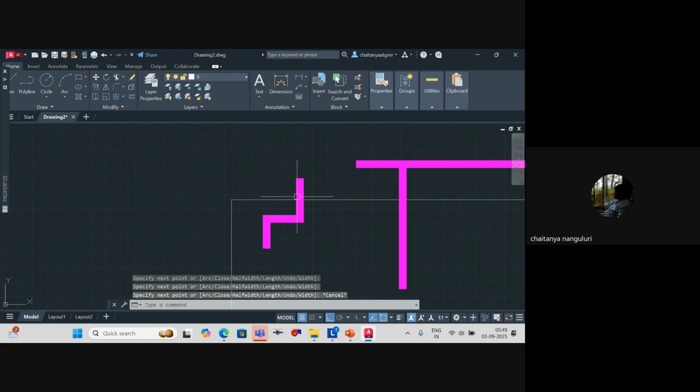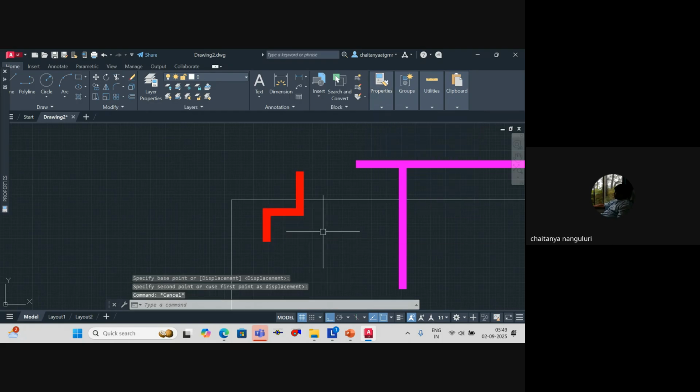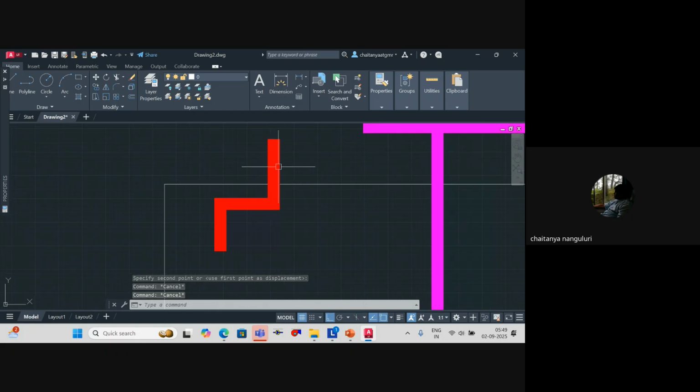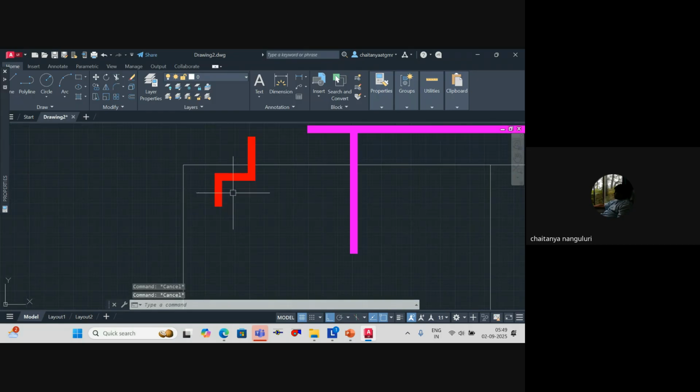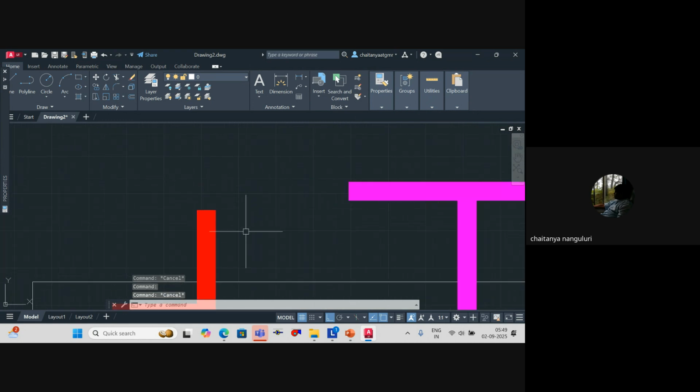So your damper will be something like this. I'll make it with another color. We'll make this crosstalk something like this. When we make this Z piece, the air is forced to go through this duct like this, and in this duct we will do complete acoustic insulation, which will absorb noise, so that whatever the return air is, all the noise is completely removed. Understood or not?